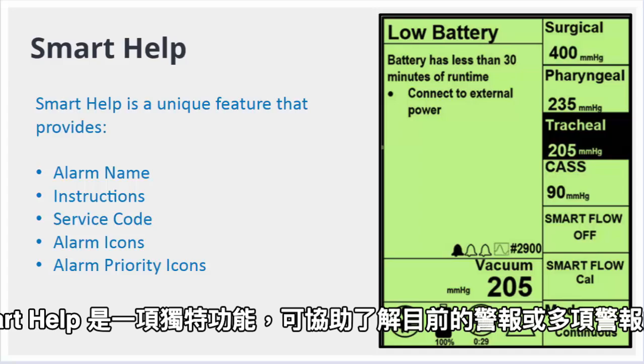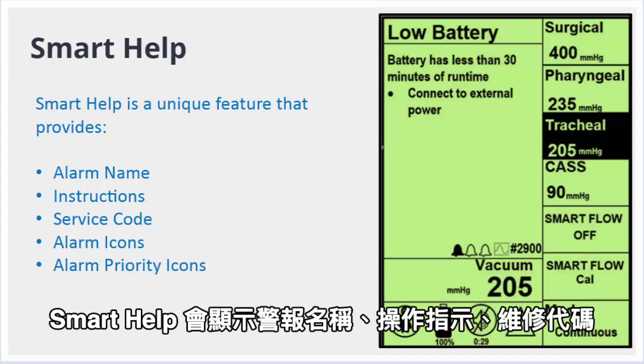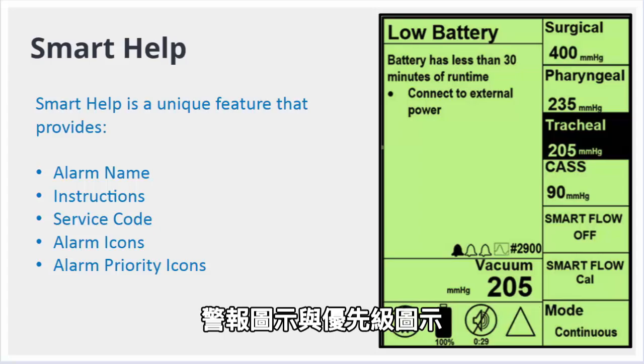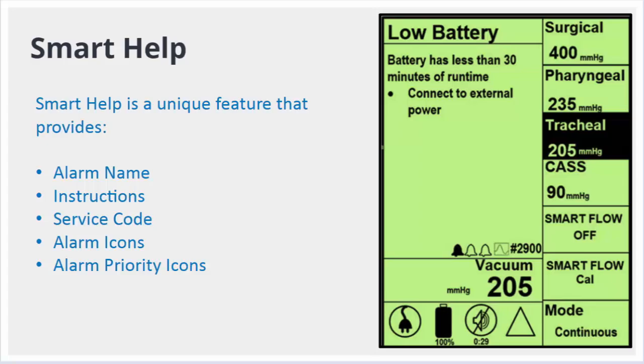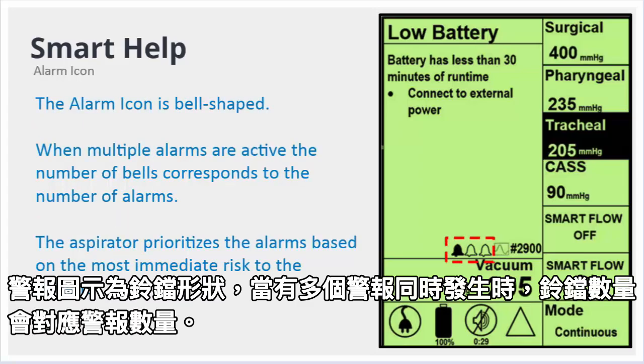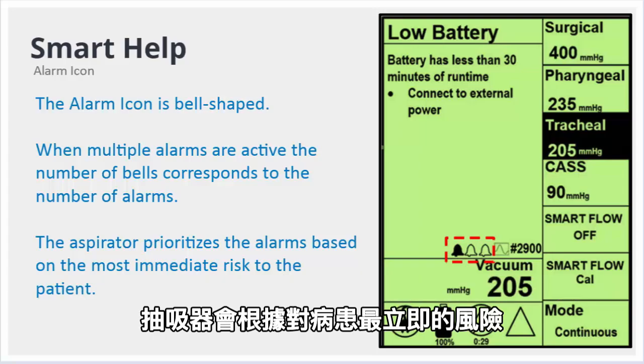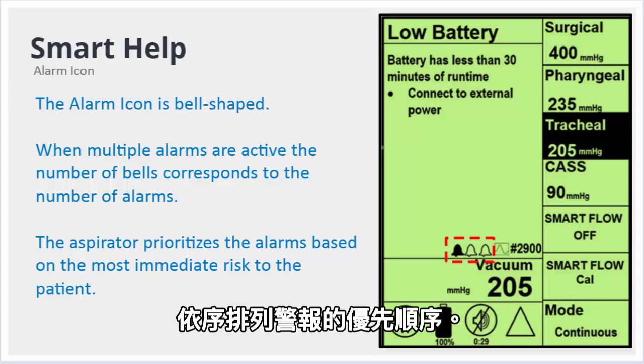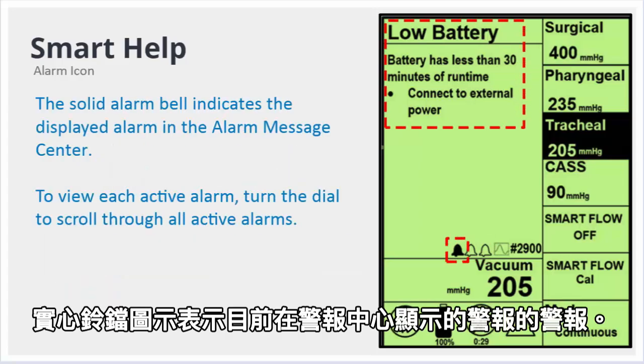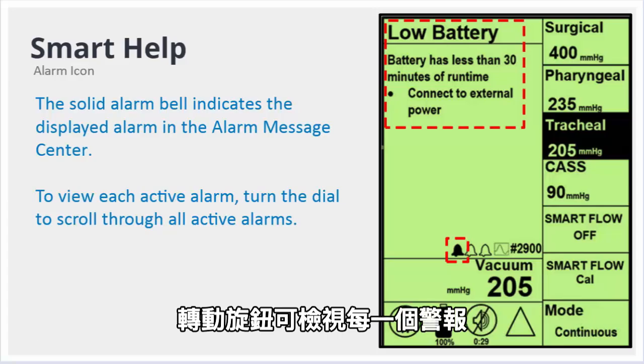Smart Help is a unique feature that supports understanding of the active alarm or alarms. Smart Help provides the alarm name, instructions, service code, alarm icons, and priority icons. The alarm icon is bell-shaped. When multiple alarms are active, the number of bells corresponds to the number of alarms. The aspirator prioritizes the alarms based on the most immediate risk to the patient. The solid alarm bell indicates the displayed alarm in the Alarm Message Center. To view each active alarm, turn the dial to scroll through all active alarms.